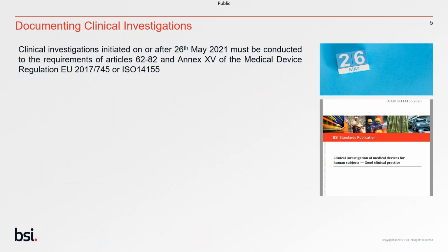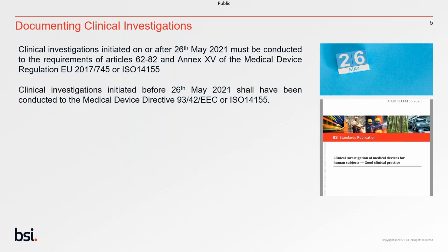So the 26th of May 2021 was obviously a very important date, but in the context of clinical investigations, it was important that any clinical investigation initiated on or after the 26th of May needs to fulfil the requirements of Articles 62 to 82 of the MDR and Annex XV. That said though, there is MDCG guidance that talks about the fact that clinical investigations initiated before the 26th of May 2021 should have been conducted to the Medical Device Directive or ISO 14155.